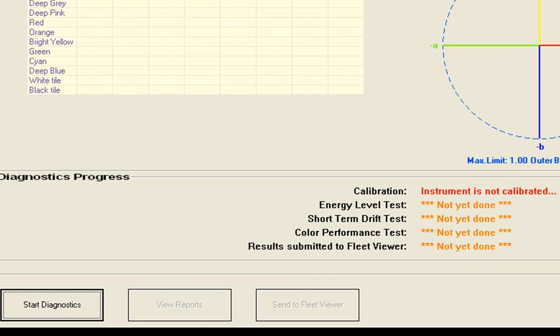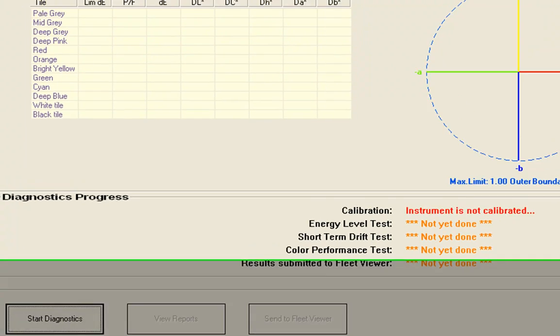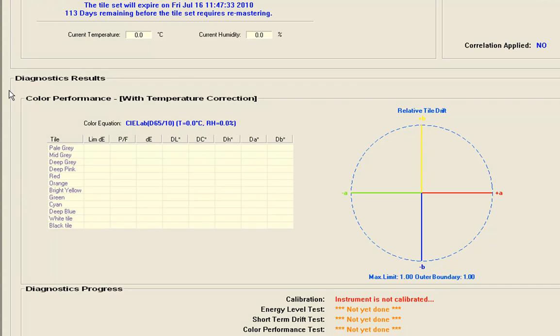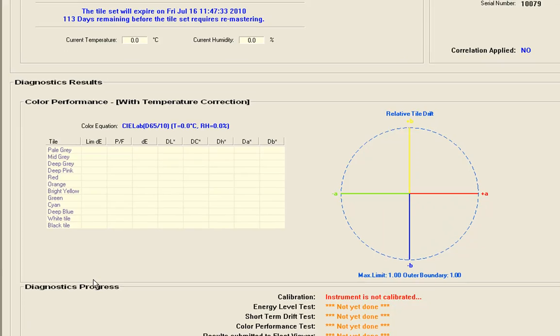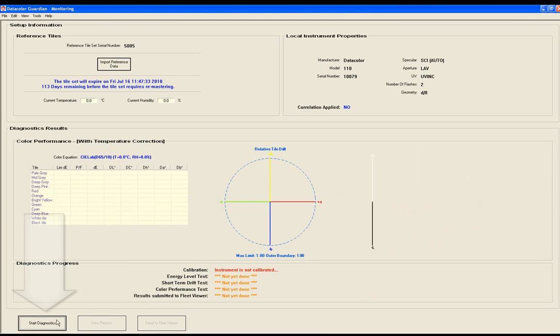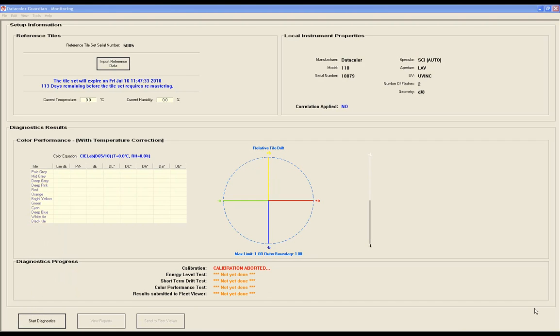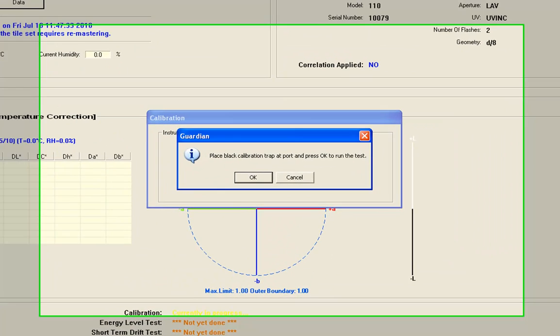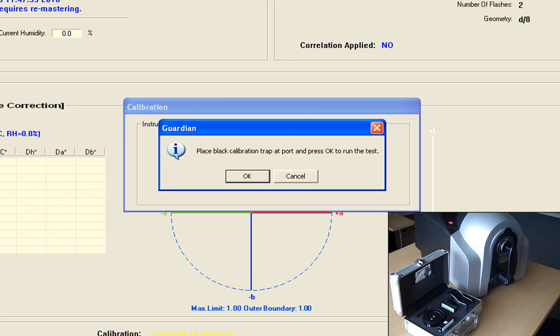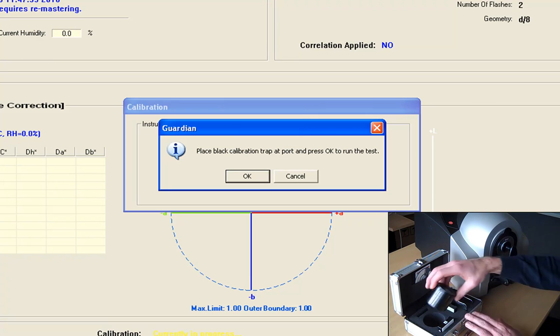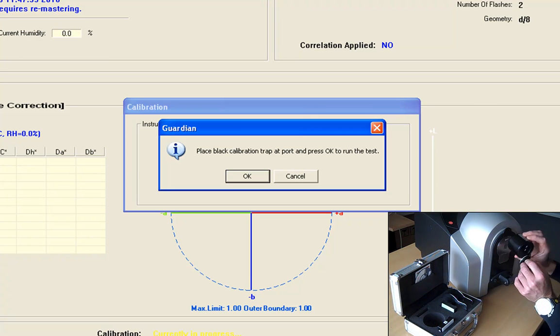At the bottom of the screen we see the diagnostic progress. For the moment none of them is done. And in the middle of the screen we see the diagnostic results. For the moment empty. So let's start the diagnostics by hitting the correct button. The first action is to present the black trap and white calibration tile. In fact, this is a normal calibration.